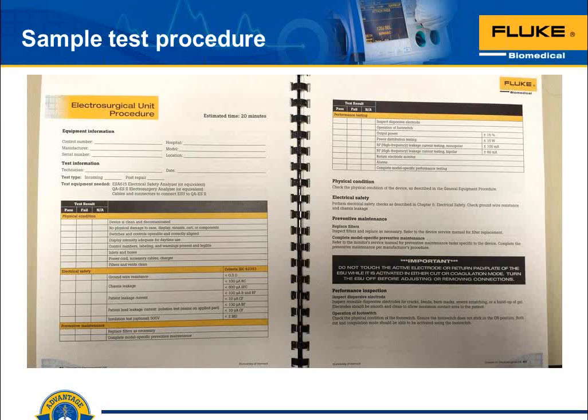Performance and calibration verification. So this is going to include operational testing of the ESU's foot switch and the alarms of the device. It will include output power tests based on some number of settings that you select or the manufacturer has described. For those ESUs that include impedance sensing circuits for output power guarantee, those circuits and algorithms need to have more than one test load value that you're providing that output power to. Otherwise, you can't really tell if those circuits are working.